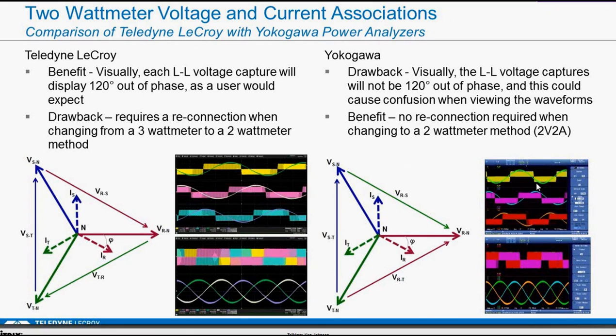So when I look at all these signals, the voltage and the current, you might say, how come the phase angle seems really way different on all these different voltages compared to all the currents? It's not the same. And the reason is just because of the connection method. The calculations are still correct. The nice thing is when you convert from a 3-wattmeter to a 2-wattmeter calculation, you don't have to reconnect anything. So that's one advantage to it.